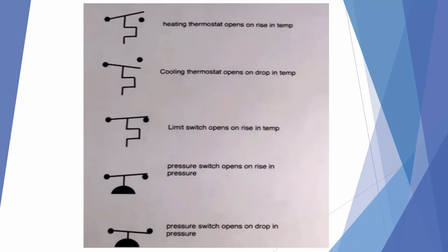As we said, these various switches can be configured in different ways. This switch on the top is a heating thermostat, which opens on temperature rise. The second diagram is a cooling thermostat, which opens on a drop in temperature. The third is a limit switch that opens on rise in temperature. The fourth is a pressure switch, which opens on rise in pressure. And the last one is a pressure switch, which opens with a drop in pressure.